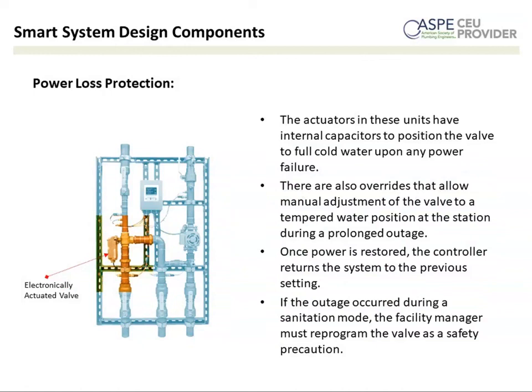Again, this question came up, so we probably don't need to harp on this slide for too long. But just to reiterate, in terms of power loss, the actuator will go to full cold, and there is a manual reset button right about where that red arrow is pointing, where you can manually adjust the valve to a tempered water selection. And when power is restored, there's non-volatile memory in the controller, so all the settings would come back. You wouldn't have to reprogram anything. The NVM will do that for you.